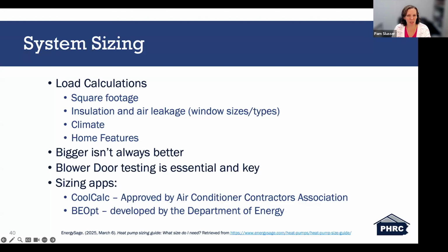Something that surprises a lot of people: bigger isn't always better. Oversizing a system can lead to short cycling, as I had stated earlier, which means that the system will be turning on and off more frequently, wasting energy. This is why blower door testing is such a valuable tool. It helps to measure how leaky a home is, giving us real data to inform system design rather than guesswork.